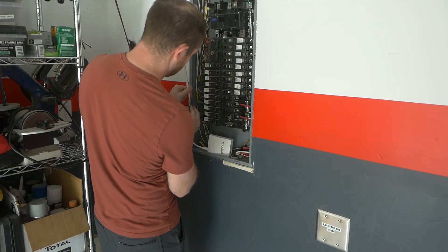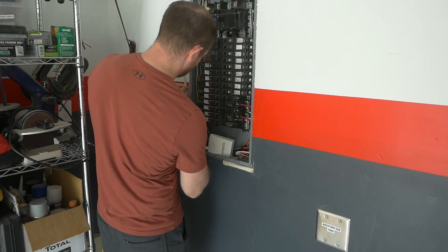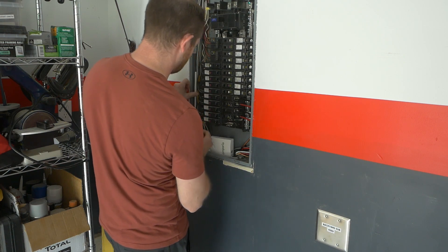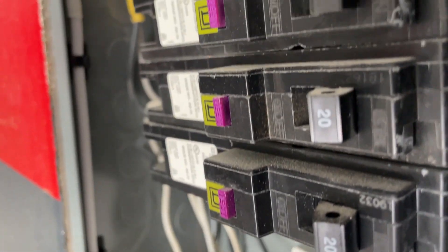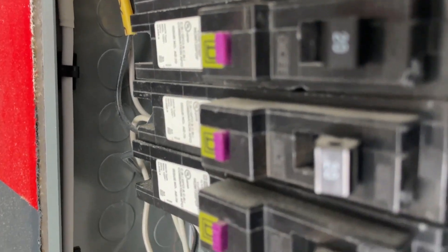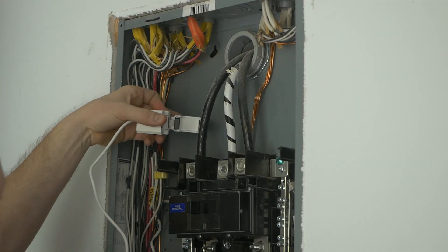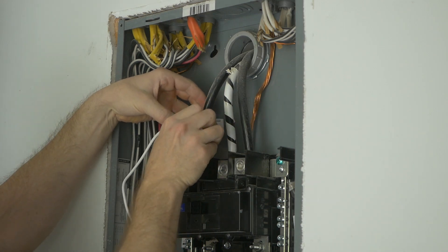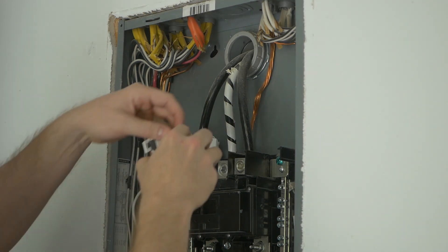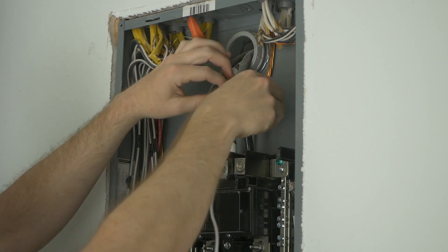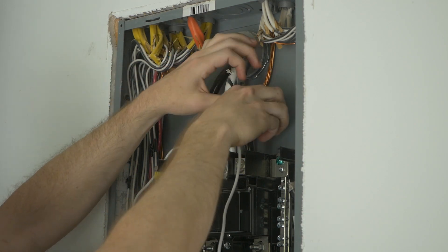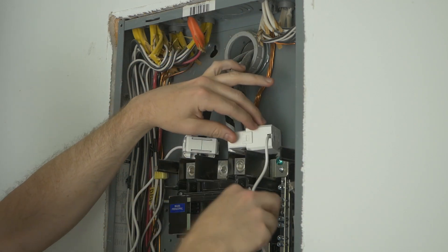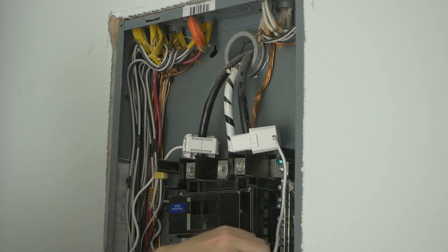We start by installing the antenna. According to the instructions, this is supposed to be outside the panel, but as mine is recessed that would be difficult so I'm just mounting it inside. However, spoiler alert, this didn't work. Next we clamp on the 200 amp current monitors. In my opinion, this is the riskiest part of this install because as I previously mentioned, flipping the main breaker only de-energized the panel below, and thus we're working around live wires. So be very careful here.